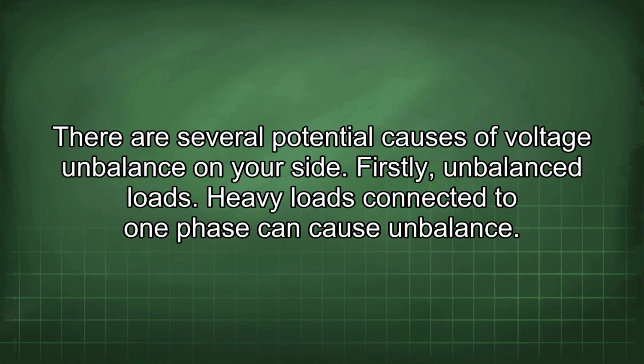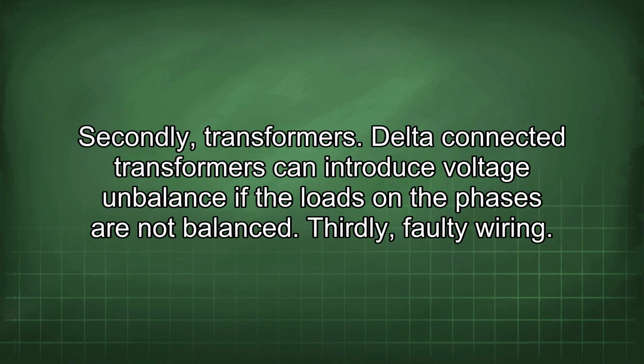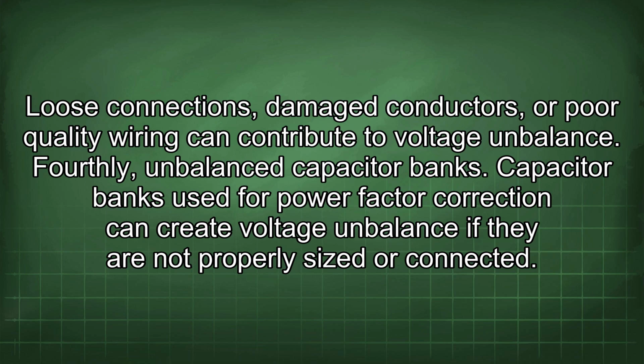There are several potential causes of voltage imbalance on your side. Firstly, unbalanced loads. Heavy loads connected to one phase can cause imbalance. Secondly, transformers. Delta-connected transformers can introduce voltage imbalance if the loads on the phases are not balanced. Thirdly, faulty wiring. Loose connections, damaged conductors, or poor quality wiring can contribute to voltage imbalance. Fourthly, unbalanced capacitor banks.